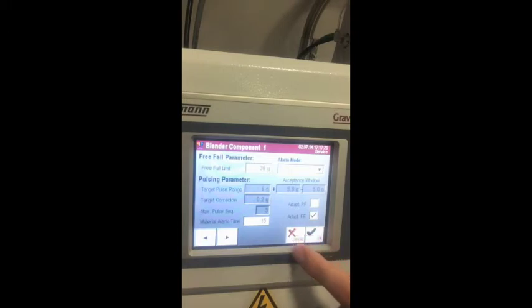The component folder allows you to create and edit recipes. The parameter folder lets you choose between various components and define the parameters for each specifically. If the target value of a component exceeds the free fall limit, a free fall is carried out; if it is less than the free fall limit, free fall is not performed. The target pulse range specifies the offset to be achieved by pulsing. The target correction indicates the shift of the offset. The maximum pulse sequence specifies the maximum number of pulse sequences used to achieve the target weight, with the actual weight measured between sequences. The material alarm time specifies the window of time to recognize whether material is present.